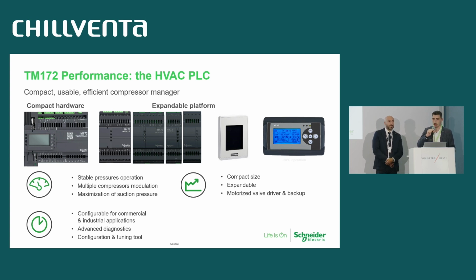These logics guarantee stable pressure operation, which is very important to achieve the required efficiency level. They can also modulate several compressors, another feature that saves energy by having the exact required load at each moment.